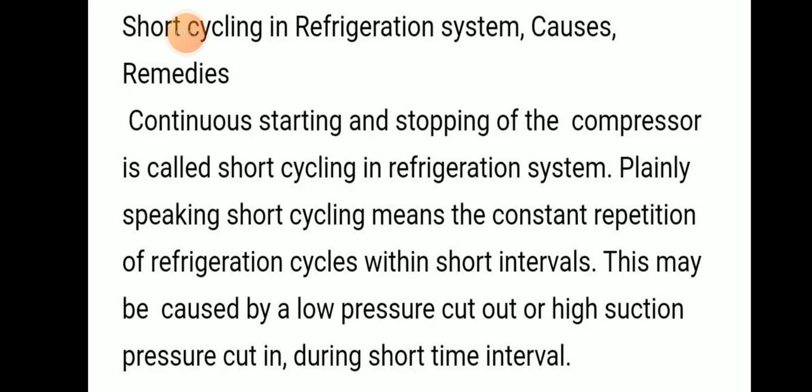Short cycling in a refrigeration system means continuous starting and stopping of the compressor. In other words, it is a constant repetition of the refrigeration cycle within short intervals. This may be caused by low pressure cutout or high suction pressure cut-in during a short time interval.